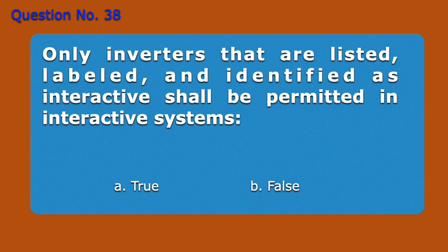Question number 38. Only inverters that are listed, labeled, and identified as interactive shall be permitted in interactive systems. A. True. B. False. Answer A. True.